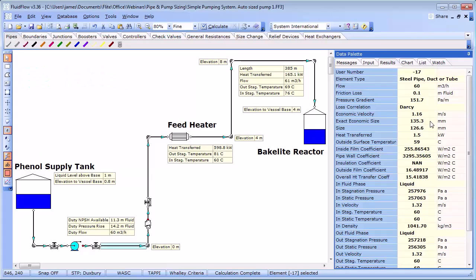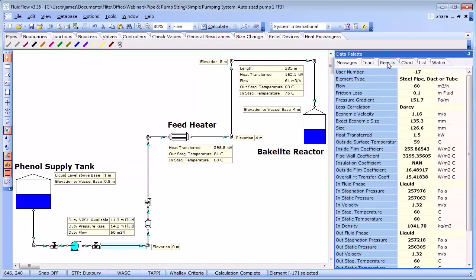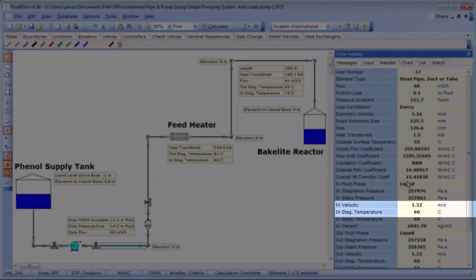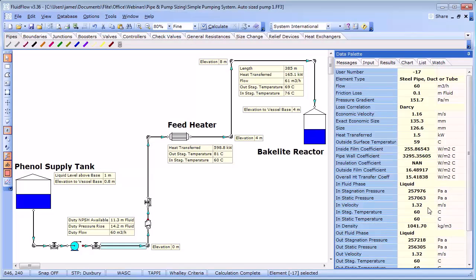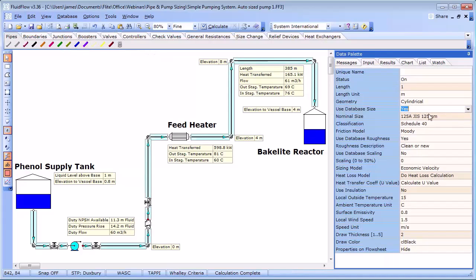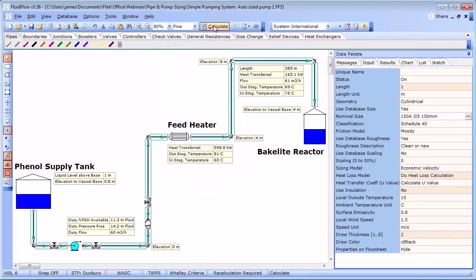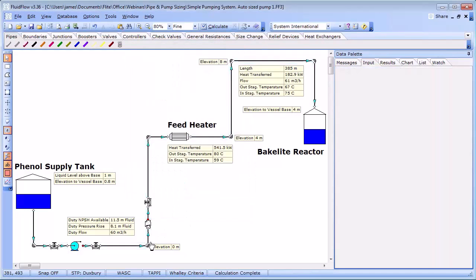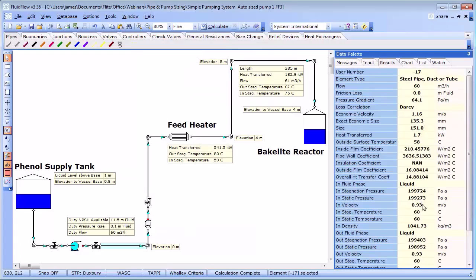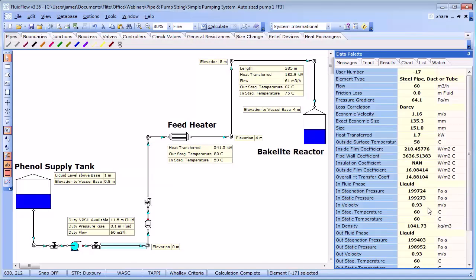By calculating the model the software has determined an economic velocity of 1.16 meters per second which gives us an exact economic pipe size of 135.3 millimeters. Using the near standard pipe size to 135.3 millimeters for steel pipe work means we either choose a 125 or 150 millimeter pipe. Using a 125 millimeter pipe gives us a velocity of 1.32 meters per second. We can increase this pipe diameter to 150 and the velocity is reduced to 0.93 meters per second.